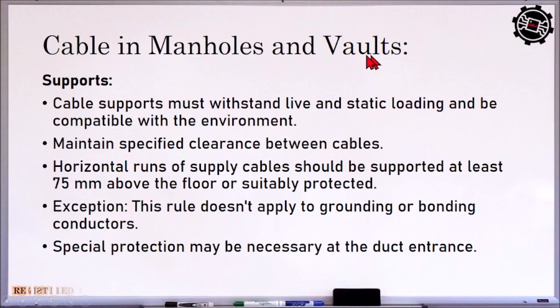Okay, so cable in manholes and vaults. So supports. Cable supports must withstand live and static loading and be compatible with the environment. So the support inside our manhole should be able to withstand the static load, meaning the actual weight of our cable, including the weight of the cover on top, or the live load, the traffic that passes over the manholes or vaults.